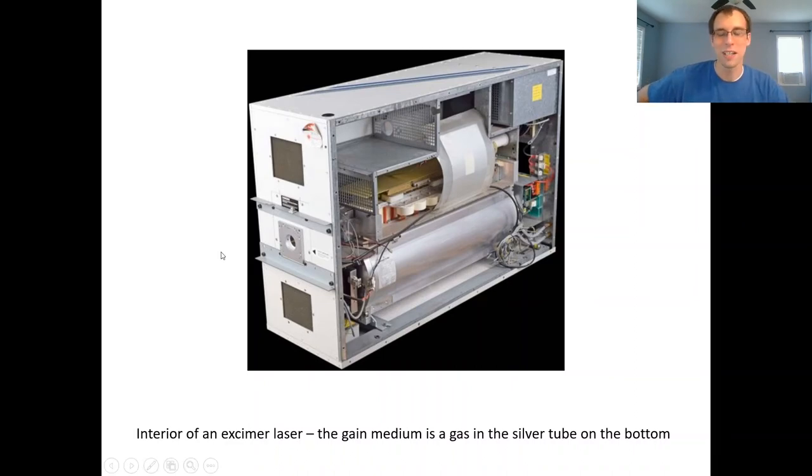You also have to make sure you don't have any leaks in this, because excimer lasers tend to use pretty toxic gases, things like fluorine and chlorine, along with noble gases like xenon. So yeah, excimer lasers are pretty interesting.